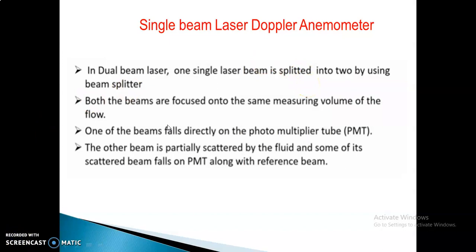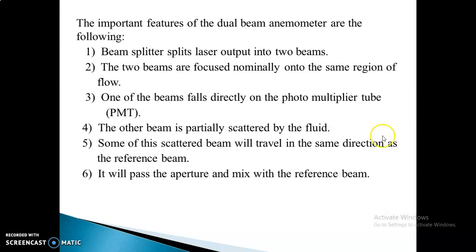In dual beam laser, one single laser beam is split into two using a beam splitter, then focused so that it falls directly to the PMT. The important features of dual beam: the beam splitter splits the laser, then those two beams are focused on the same region of the flow. One of the beams falls directly to the PMT; the other is partially scattered, and some of the scattered light travels in the same direction as the reference beam. It then passes through the aperture and mixes with the reference beam.